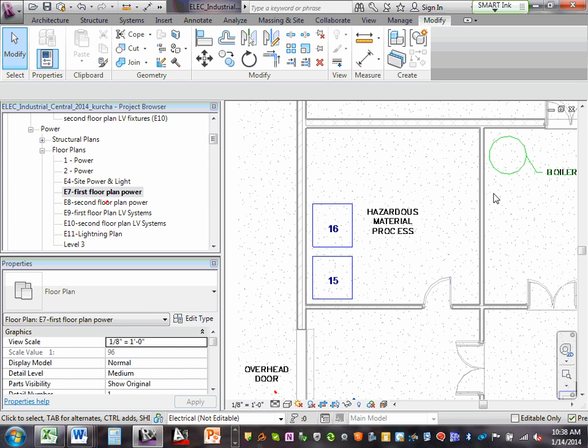Okay? An explosive atmosphere, whether it be gas, fumes, or dust, which can be explosive, with the granary fires and explosions that happen frequently out there in America. What we're talking about is eliminating the potential for electrical arc. So, number one, all the wiring has to be in rigid conduit. That's got to be sealed, with threaded connections sealed tight.